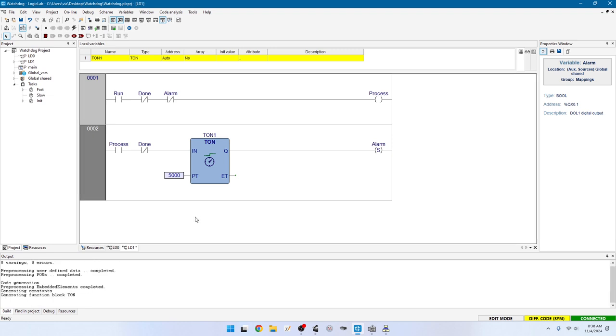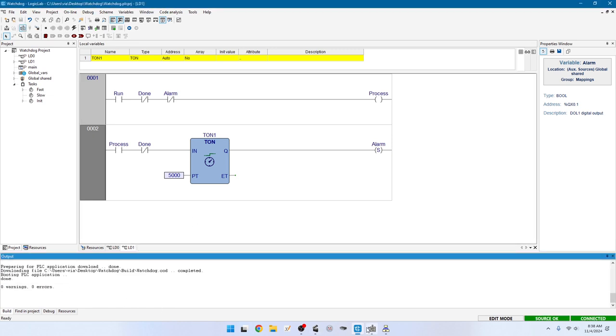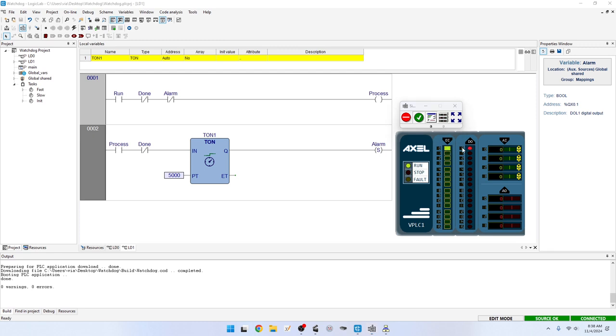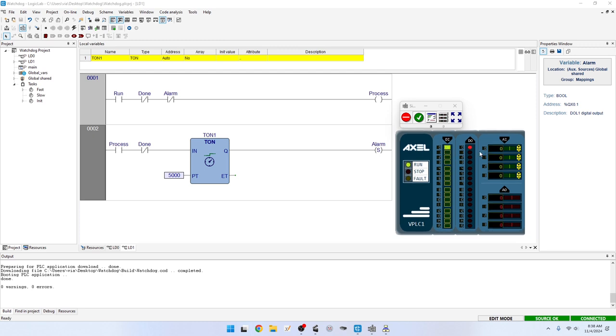F7, F5 — let's run now. After five seconds, the process turns off and the alarm turns on, and now it stays off. Even if I press done, it stays set. This is locked unless I have an explicit reset or I reset the PLC. If the process finishes in less than five seconds with done being true, no problem. But if you exceed five seconds, the process turns off, the alarm sounds, and we're locked out until we restart.